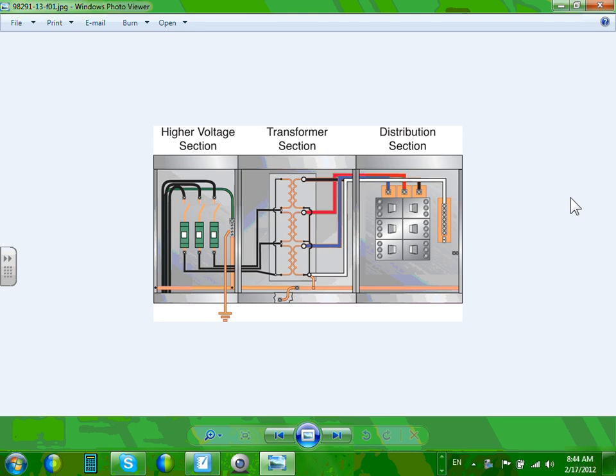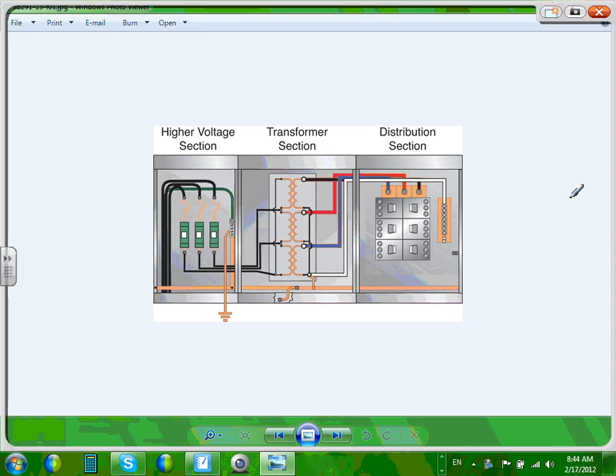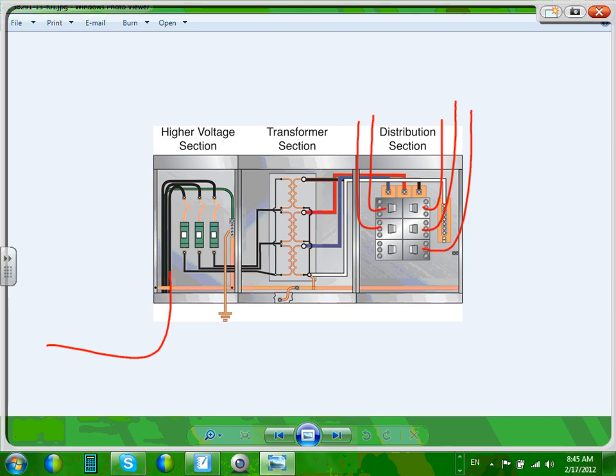What you would do with this, guys, is you bring your high voltage cables in, as you can see, and then you get your low voltage cables out. In this case, you will be getting your low voltage cables out of all these, and you go inside your building. Okay? So, where would you use something like this? Notoriously famous, guys, in hospitals, where you have a substation like this. With a high voltage, we have a hospital, I believe in Mayo Clinic, they took a 13.8 feeder from the basement all the way to the 13th floor, and they fed everything down with that 13.8.